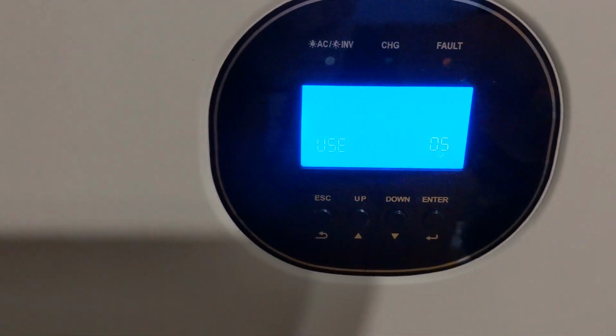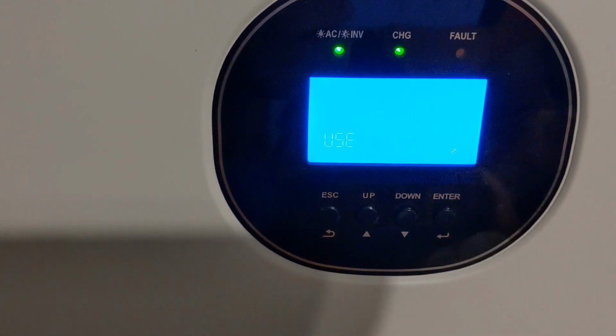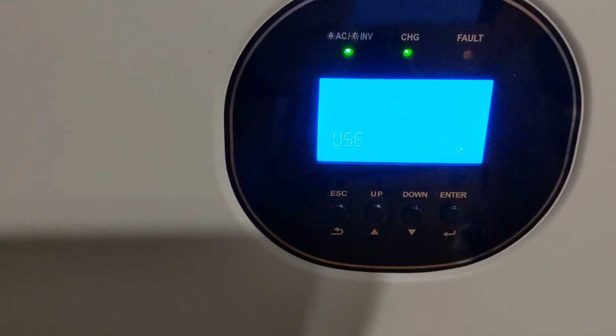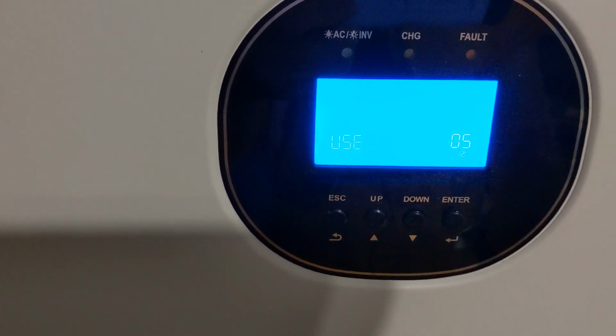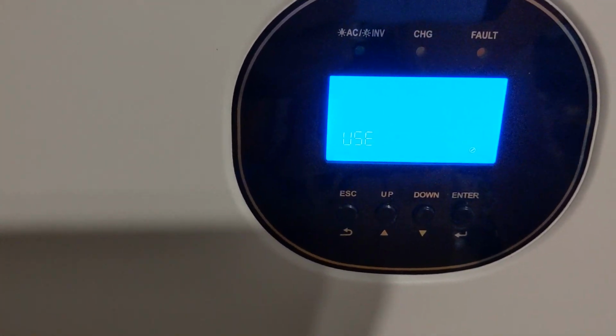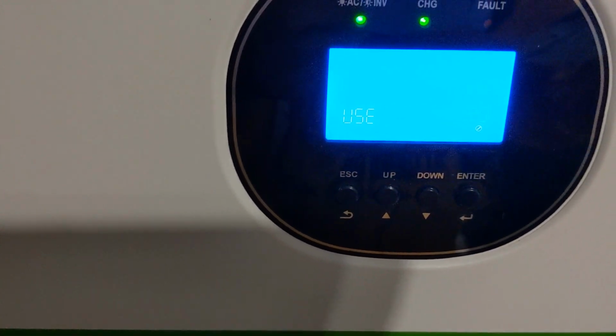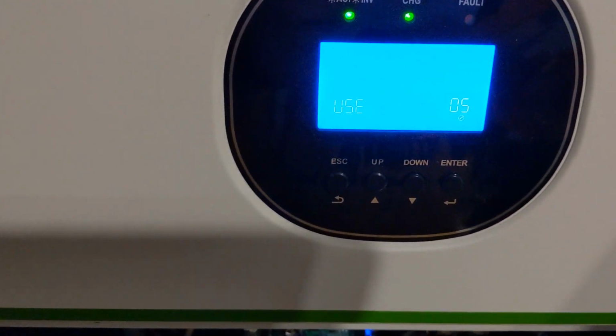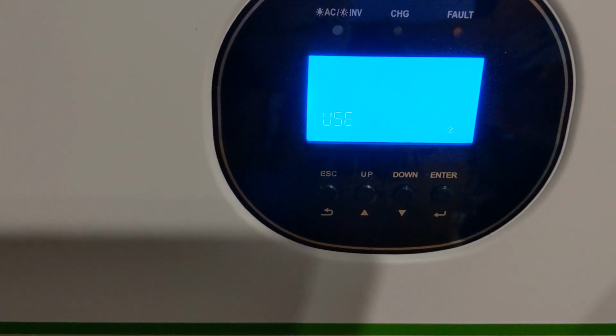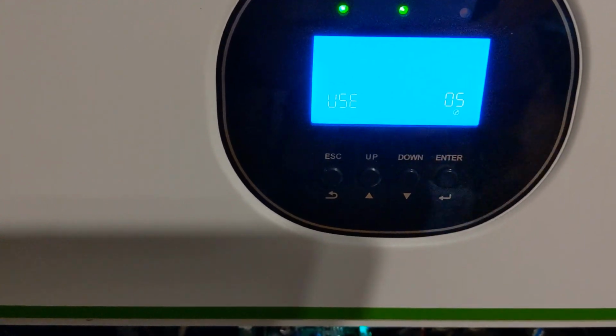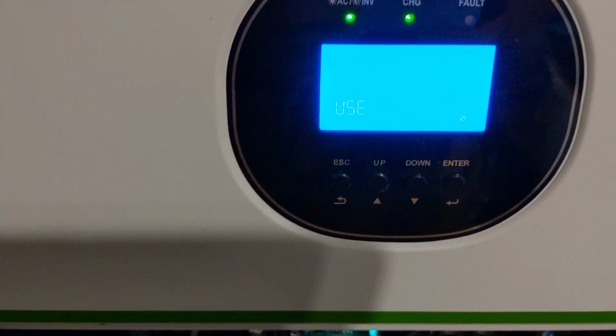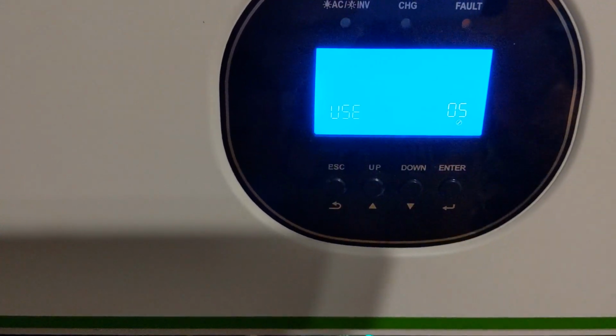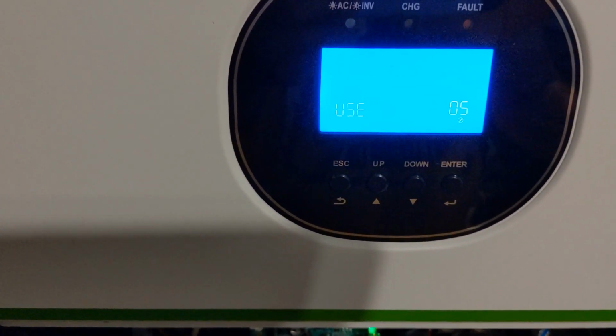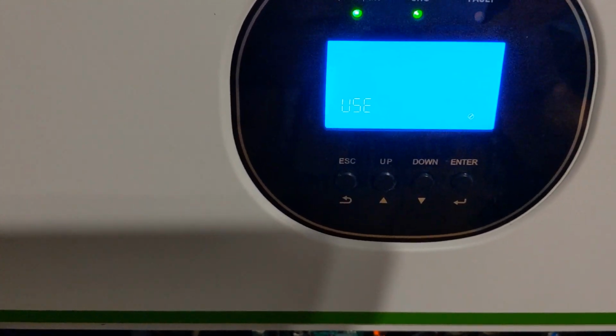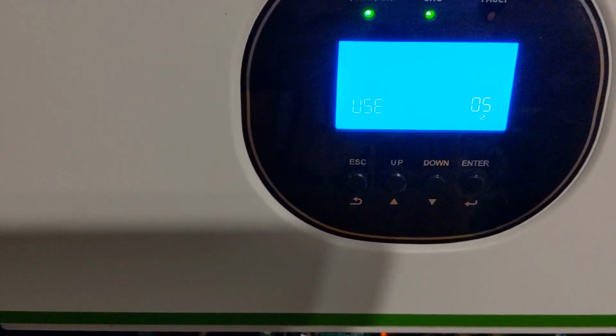Now this is the battery type, and so you can see I've got this on user mode, which is user defined. User defined allows you to set your settings for lithium type chemistries versus your normal basic chemistry settings that it has in here, which are either AGM or flooded. They also have a lithium section, but that is specifically for batteries that are designed to talk to this particular one with its little interface. That doesn't work with just general lithium. For anything custom, use your user defined, and then that allows you to set all your individual voltages.